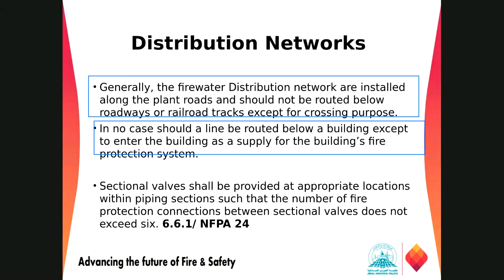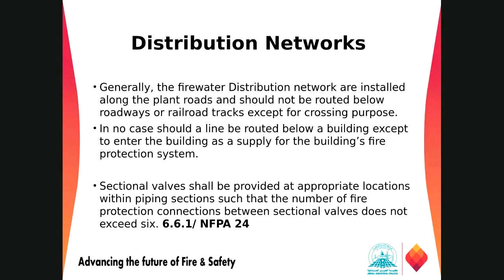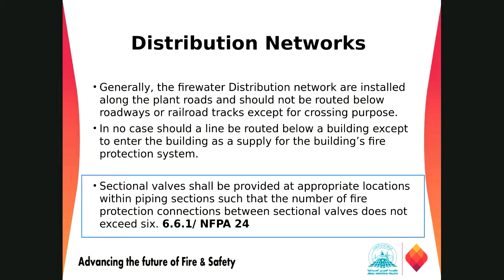And we need a sectional control valve, right? The sectional control valve is required as per 6.6.1 of NFPA 24. This says that we need a sectional valve at appropriate locations within the piping system, so that in any case the number of fire protection equipment or connections should not be more than 6.